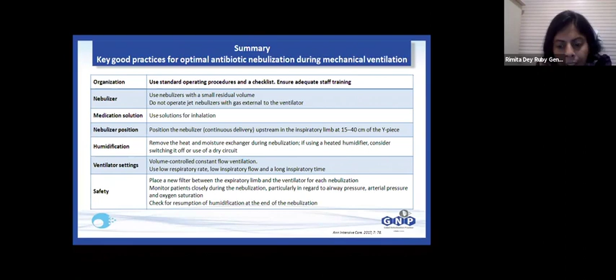Remove the HME during nebulization. If it is a heated humidifier or an active humidifier, then consider switching it off or using a dry circuit. You can change the ventilatory settings if feasible for a patient, and place a new filter between the expiratory limb and the ventilator for each nebulization. Monitor the patient closely during nebulizations, particularly in regard to the airway pressure, arterial pressure, and oxygen saturation. Check for the resumption of humidification at the end of the nebulization. So that was my talk.